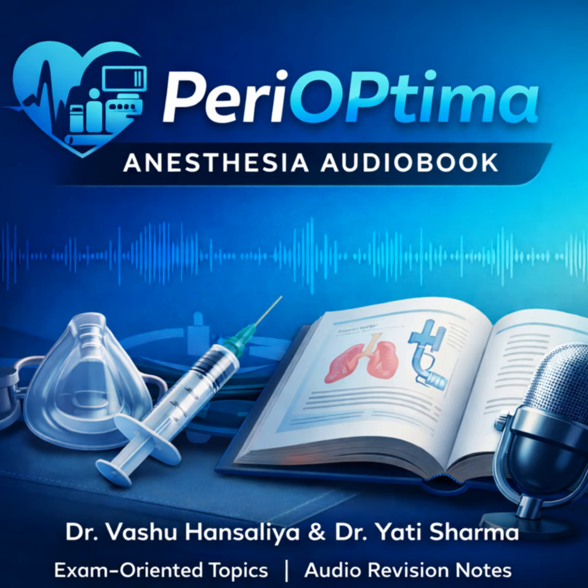So for the non-rebreathing systems? For the non-rebreathing high-flow Mapleson systems, to prevent rebreathing of CO2, your flows have to be high. We're talking 1 to 3 times the patient's minute ventilation, or MV. This is resource intensive and costly. Whereas for rebreathing systems, like the circle, it's the opposite. It's a low flow system. Since the CO2 is being removed chemically, you can get away with low flow or even minimal flow anesthesia. Your flows only need to replace the patient's oxygen consumption and the amount of volatile agent being taken up by the body.